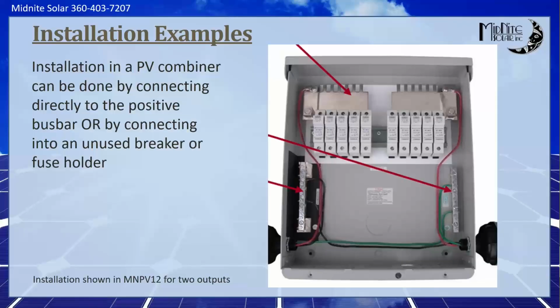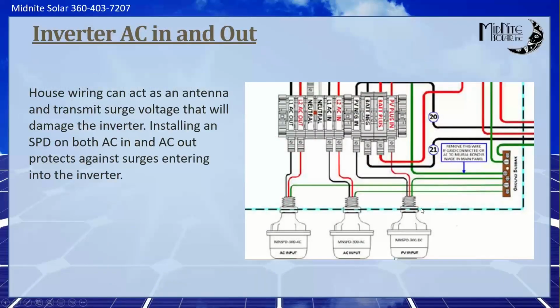The only downside to putting it in fuses or breakers for me is, let's say we come out to work on this for some reason and we lose a fuse, or some reason we break a fuse or blow a fuse. It's awful easy to rob the one out of the lightning protection because it's not actually affecting customer production. So that's the only downside. It's easy to rob. It's easy to overlook, if you will. So keep that in mind. But most all of our combiners have some provision for installing those.